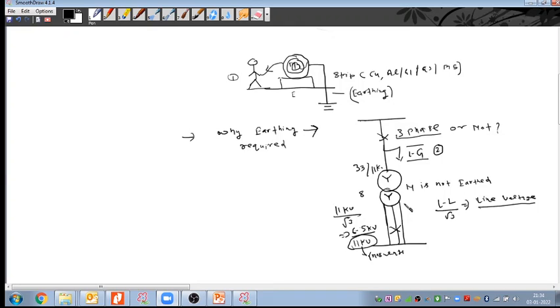All the earthing and grounding is linked to the ground fault. Out of all the types of fault, triple L, triple LG, double L, and single LG, we know these types of fault, right? We understood them during our engineering time. These are the types of fault that happen in the electrical power system. The probability of a triple L fault is very low, and this is also very low. Most faults, around 85%, are LG faults.